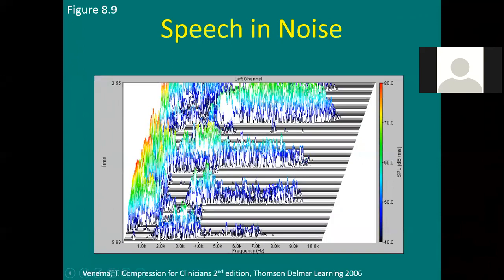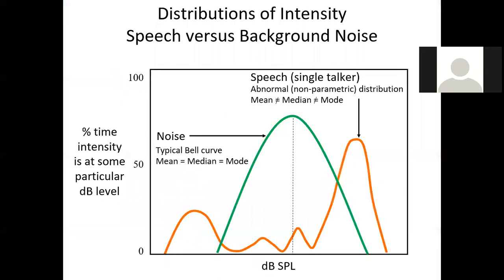If background noise comes into the picture, that's like the sea flooding the lowlands. The background noise covering the high frequency consonants. A digital hearing aid, digital noise reduction, cannot remove the water without at the same time snapping the trees. That's what I meant in the previous slide, where I said when it reduces the gain in certain channels for the noise, it's also reducing the gain for the speech. Very important to keep that in mind.